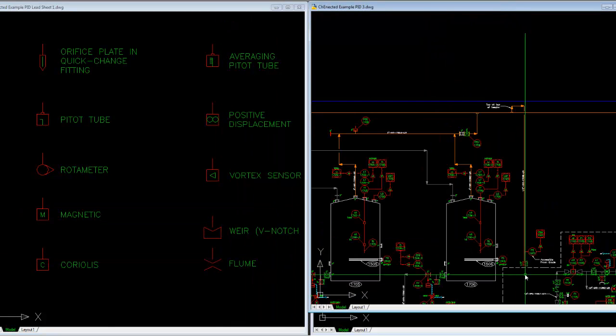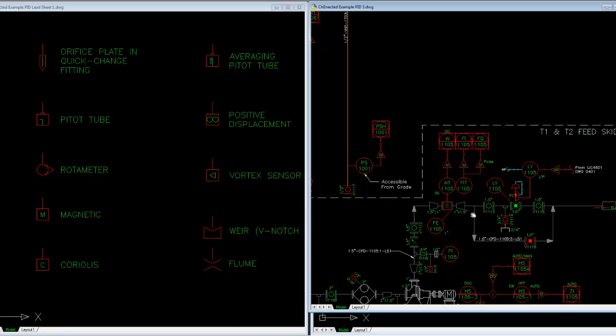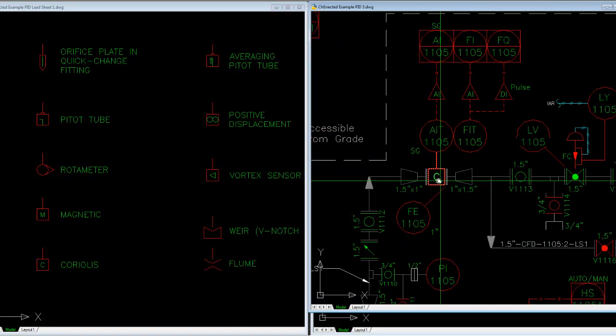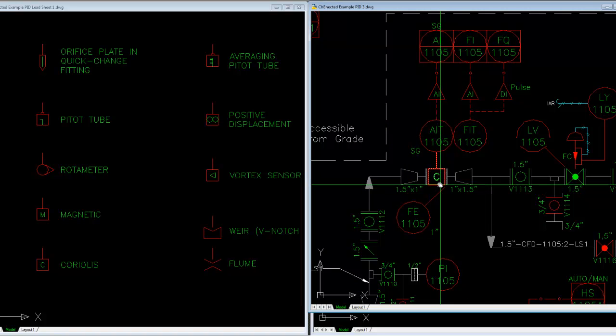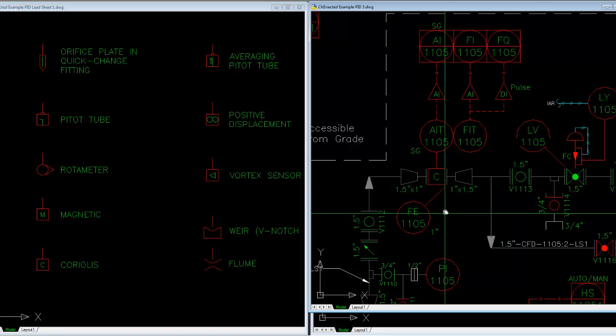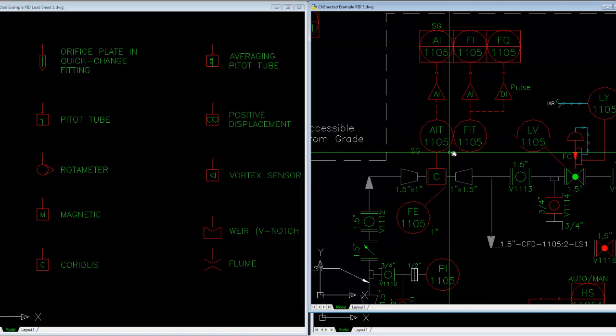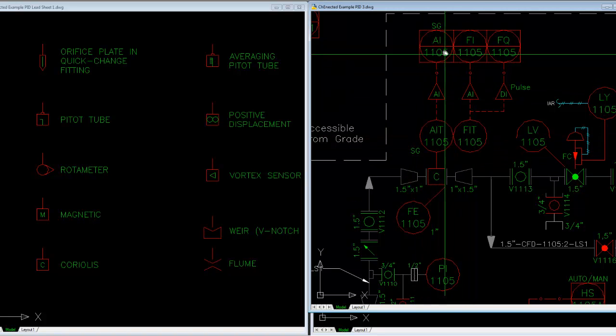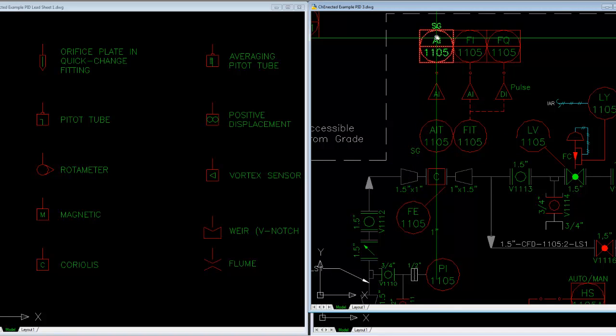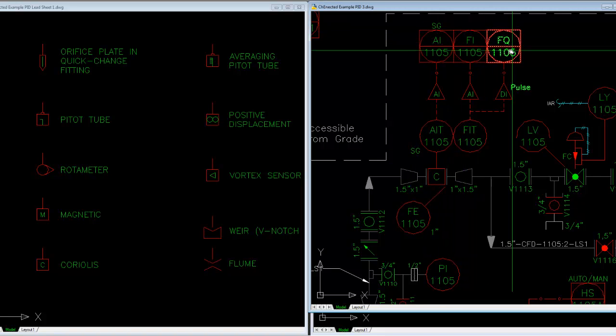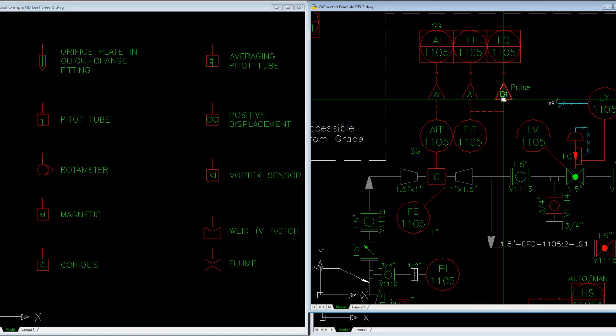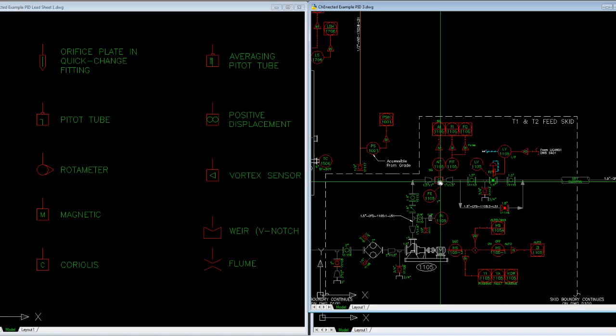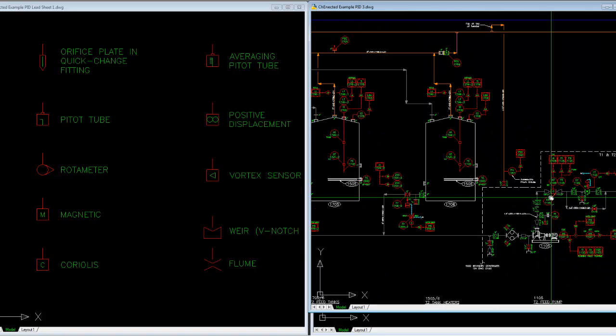So again, if you look at an application where you have a Coriolis flow meter, okay, it's a Coriolis flow meter. How's that provide any help to the operator versus it being a mag meter? Maybe not a whole lot. But what is important is that this thing has specific gravity as flow. It's indicating on the HMI what the flow is, the specific gravity of the fluid. And it's totalizing through some secondary pulse input, how much is flowing in the line.